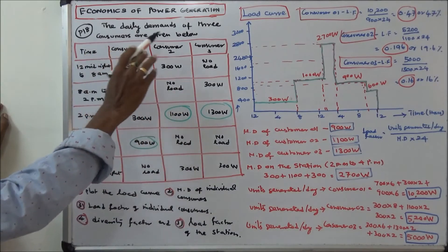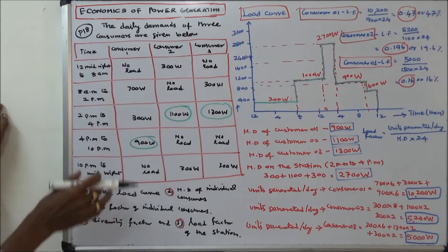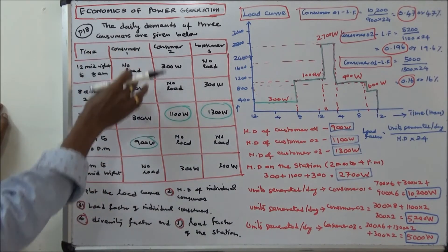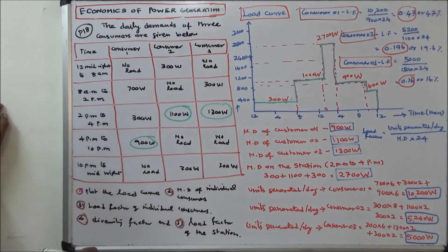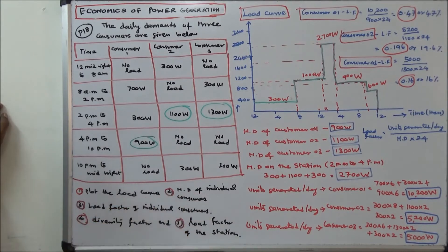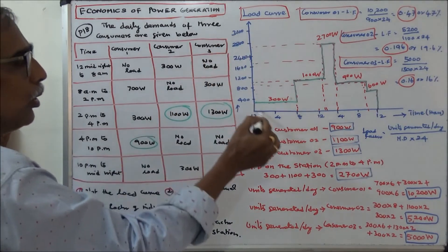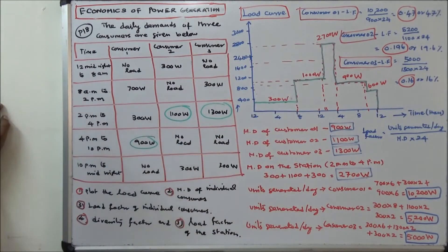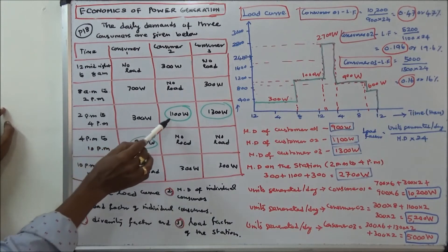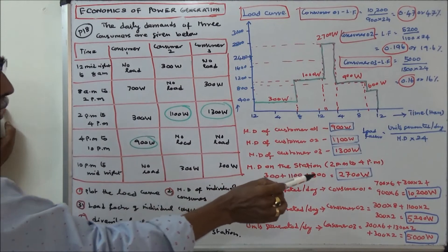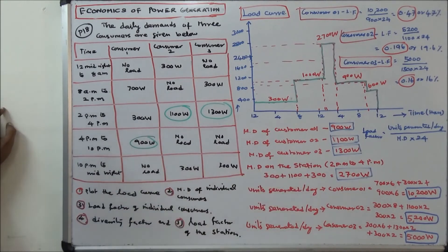Second problem: the daily demands of three consumers are given in the table. Questions: plot the load curve, find maximum demand of individual consumers, load factor of individual consumers, diversity factor, and load factor of the station. We draw the load curve. From the load curve, we find the maximum demand of the station is 2700 watts — at 2 to 4 PM: 300 + 1100 + 1300 = 2700.